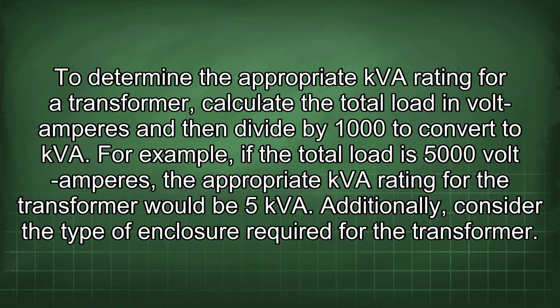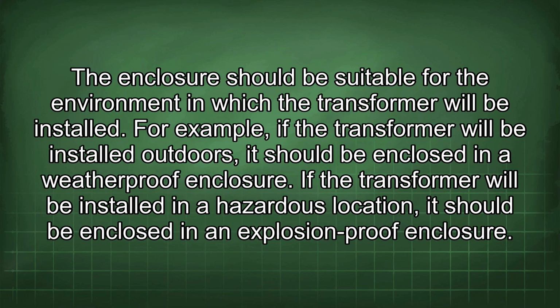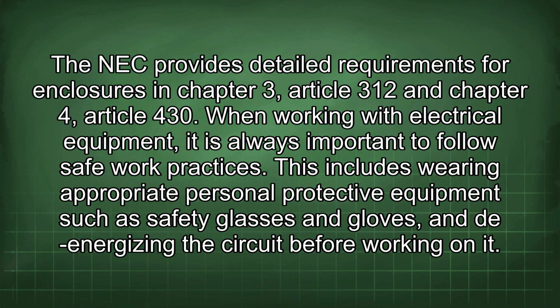Additionally, consider the type of enclosure required for the transformer. The enclosure should be suitable for the environment in which the transformer will be installed. For example, if the transformer will be installed outdoors, it should be enclosed in a weatherproof enclosure. If the transformer will be installed in a hazardous location, it should be enclosed in an explosion-proof enclosure. The NEC provides detailed requirements for enclosures in Chapter 3, Article 312 and Chapter 4, Article 430.